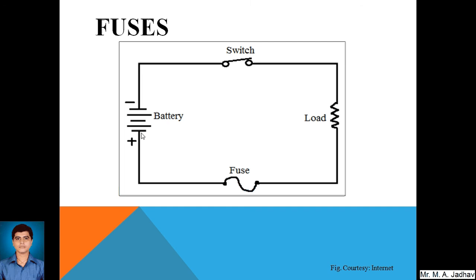Connecting the fuse on the positive side is important for human safety. If the fuse is connected on the negative side instead, there are chances that a person touching any component part of the open circuit may get an electric shock, especially if the current supplied is AC current. This is another consideration to keep in mind when connecting a fuse.